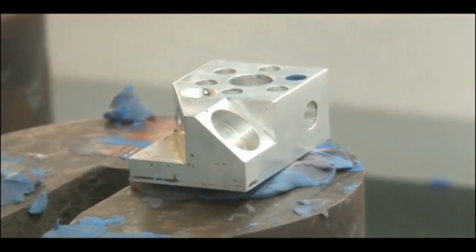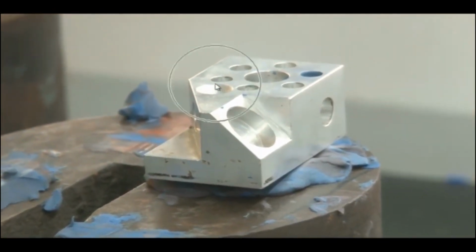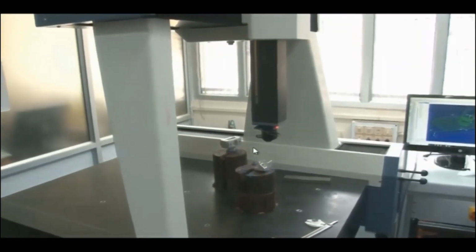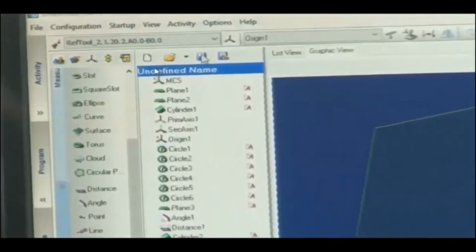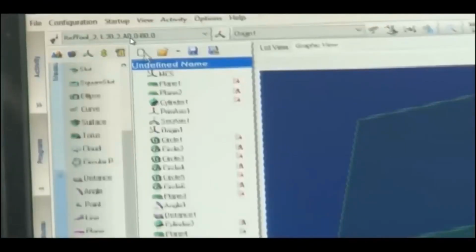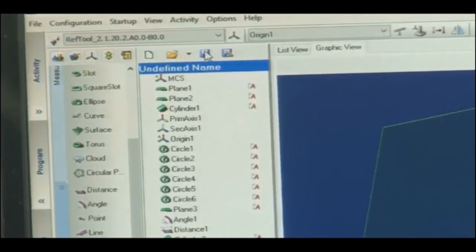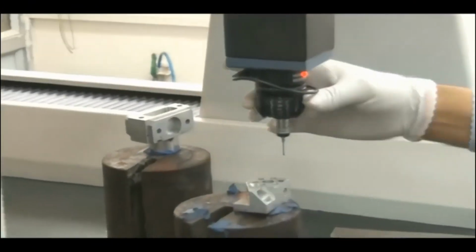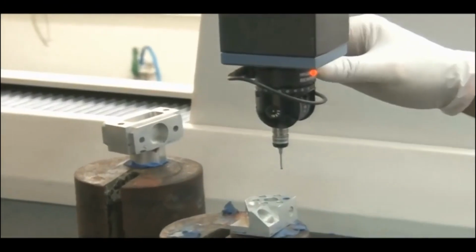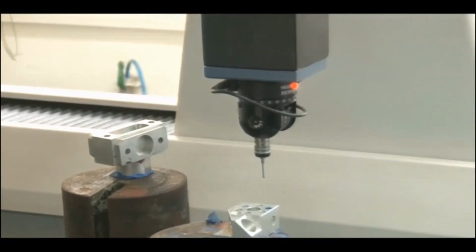Now we will measure this cone here. Again we will change the position to measure this cone. A has to come back to its 0 position. You will select A0 and B0. Click OK, yes, OK. So A is again brought to 0 position and B is again brought to 0 position. The angle is 0, 0. Lock the nut here.